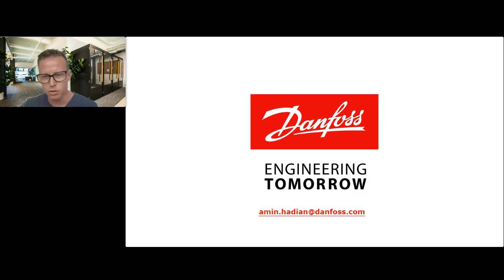It says, can the water damage the servers? What happens when water and the electronics? It's a very good question and frequently asked question, because somebody who is working in the data center environment and thinks about all those servers and all those electrical equipment and then looks at the water, they say, okay, these two things can never work together. First of all, I can answer it with the words that there are even sprinkler systems that are approved for being used in that environment. And the sprinkler system has much more water when they want to extinguish a fire compared to a high pressure water mist. So also there, they have carried out their tests without having any impact to the running electrical equipment. This is one approach or one way to explain that.